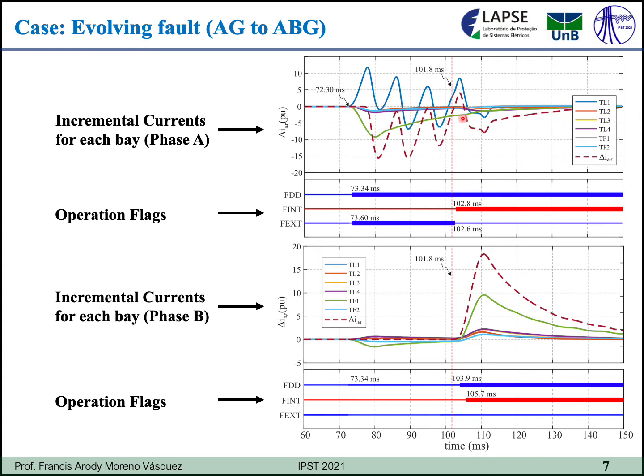On the other hand, according to the results of phase B, the behavior is similar to a simple internal fault. That is, all of the incremental signals have the same polarity and the internal fault is recognized. That is because this phase is not involved in the first moment when the external fault occurred.